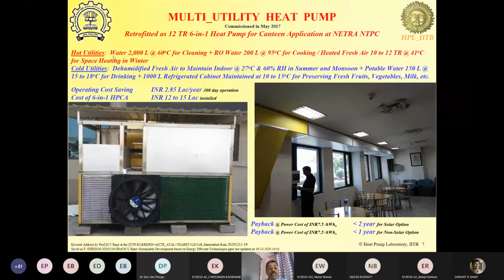And the other utilities that this system was producing were 2,000 liters of water being heated from 20 degrees to 60 degrees in a single pass, and then 200 liters of water at 95 degrees centigrade. So from 20 degrees to 95 degrees in a single pass without any pumps. All these utilities are discharged without any pump, neither during the storage phase nor during the discharge phase. So the heat exchangers are novel in that sense, and they were deployed in such a way that you could use them in that way.